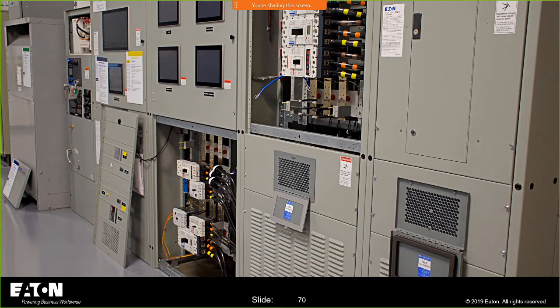Those who are in the facility probably know it's not energized. But you have to treat it all as if it is energized, because you don't have any indications on whether or not you have power, because you have to test and then retest to establish an electrically safe working condition. Remember that. You just don't turn a switch off and say it's de-energized. You have to follow the process of establishing an electrically safe working condition.